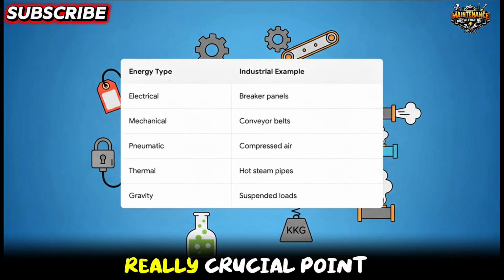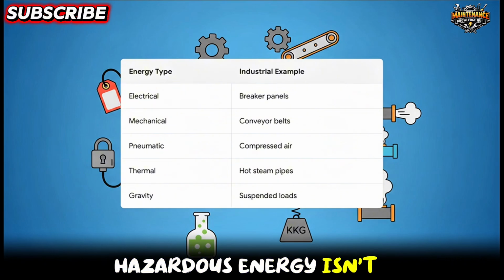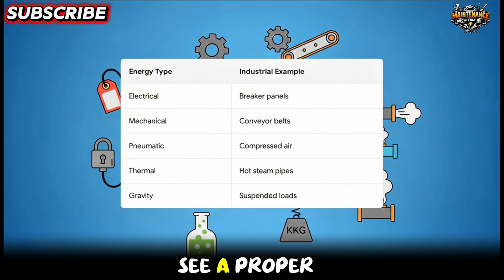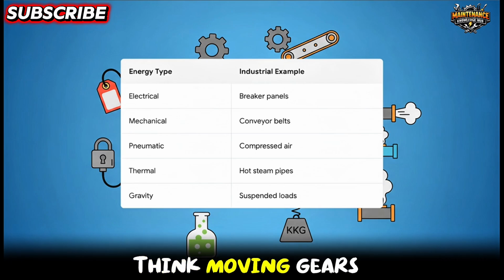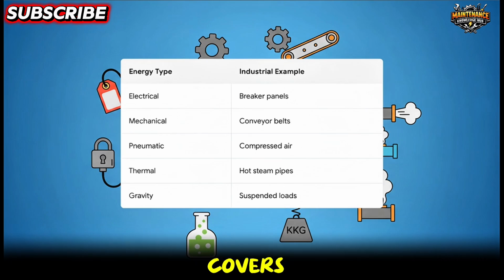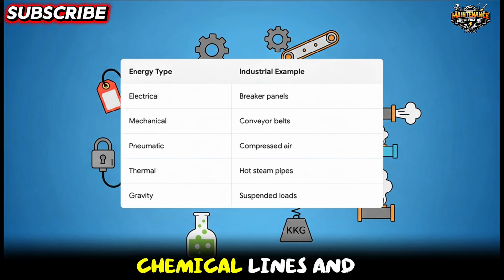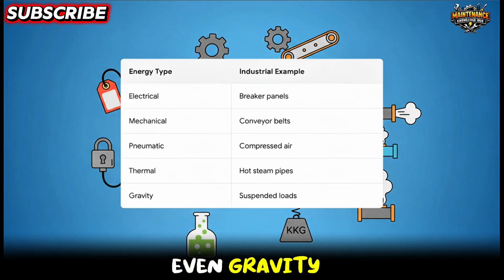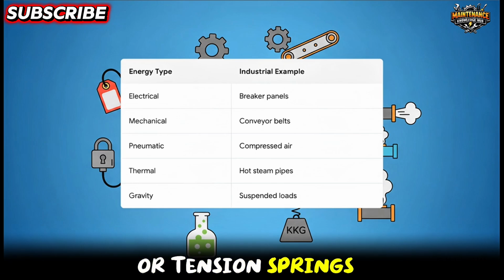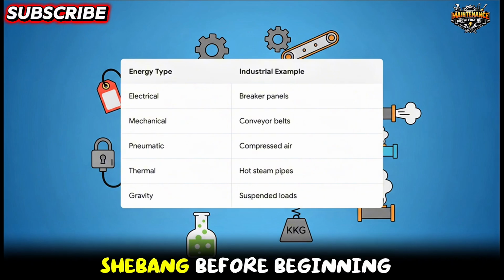Now here's a really crucial point: hazardous energy isn't just electrical. A proper LOTO procedure has to account for things like mechanical energy, think moving gears or conveyor belts. It covers pneumatic and hydraulic pressure, thermal hazards like hot steam, chemical lines, and even gravity from suspended loads or tension springs. You have to lock out all of these potential dangers, basically the whole shebang, before beginning your work.